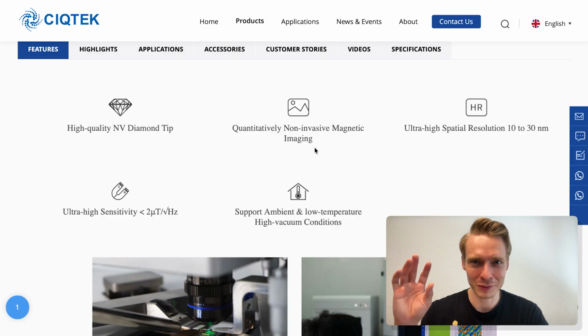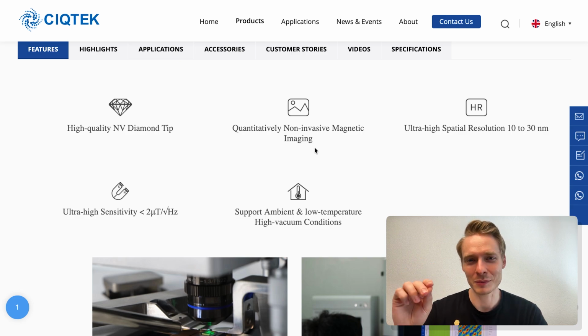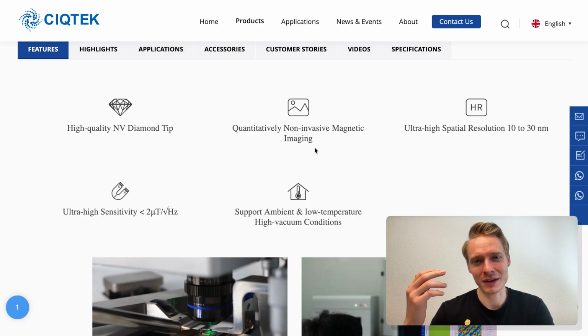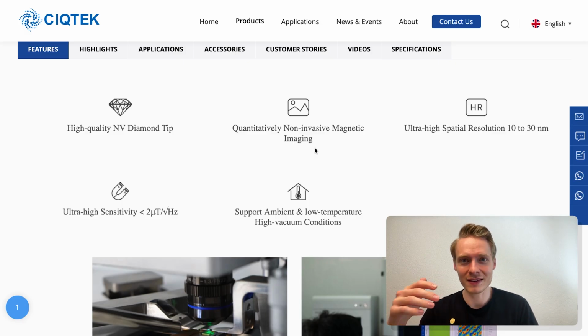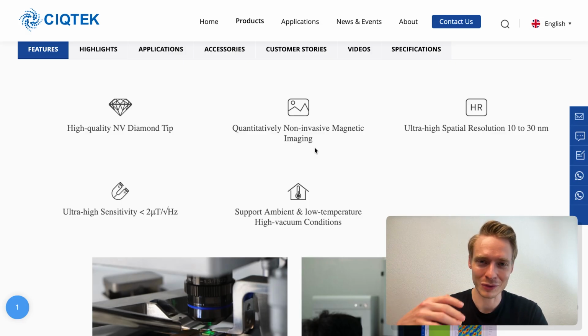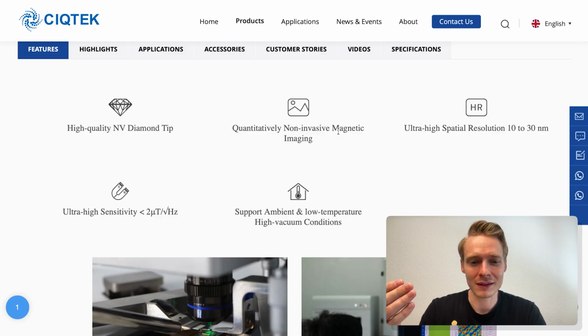Maybe also important to note the FIB that I was talking about before, right? The focused ion beam is actually ripping off materials. So the FIB is something that is invasive. It destroys the sample. You cannot put it back into original order afterwards again. Whereas here in this case, it's a non-invasive method. So it doesn't, let's say, destroy your sample. You can still use it afterwards.